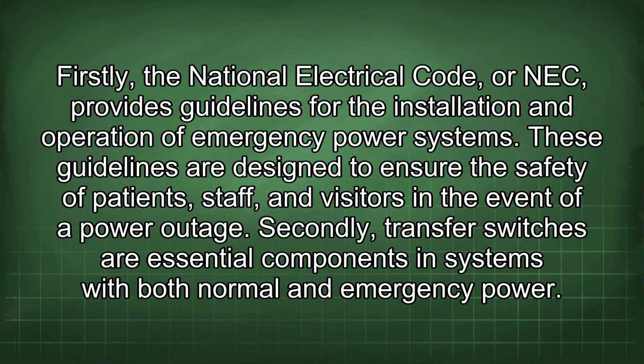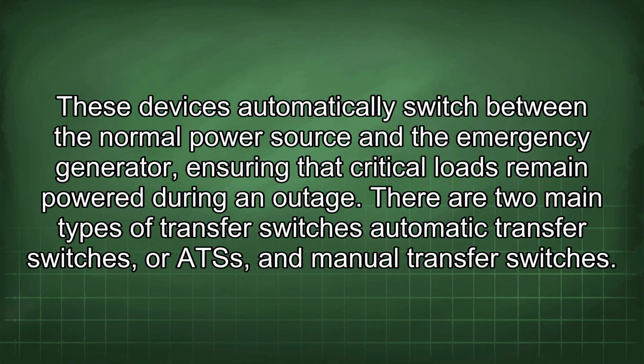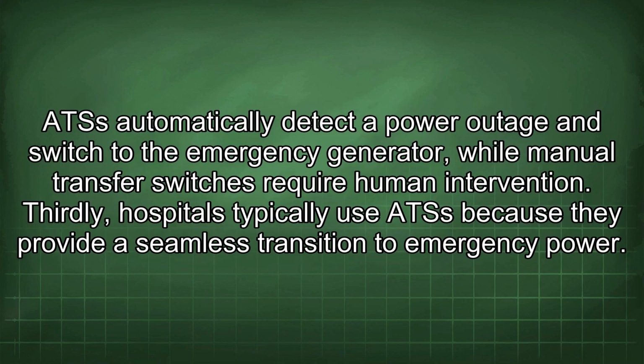Secondly, transfer switches are essential components in systems with both normal and emergency power. These devices automatically switch between the normal power source and the emergency generator, ensuring that critical loads remain powered during an outage. There are two main types of transfer switches: automatic transfer switches, or ATSs, and manual transfer switches. ATSs automatically detect a power outage and switch to the emergency generator, while manual transfer switches require human intervention.